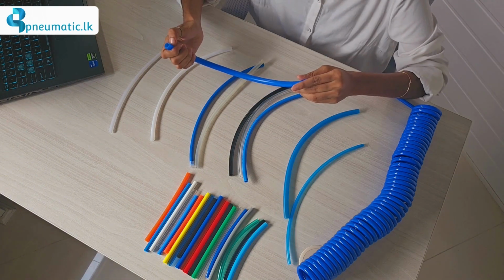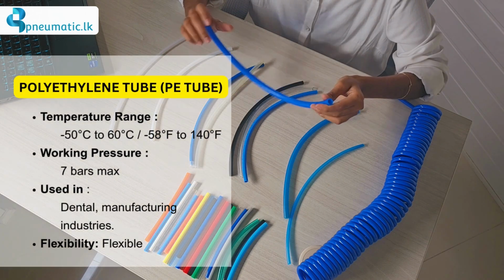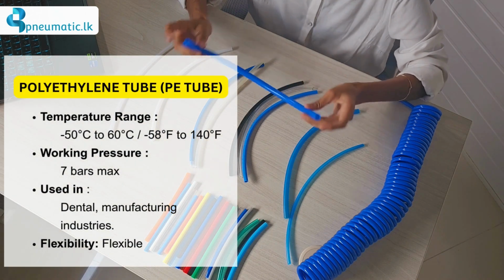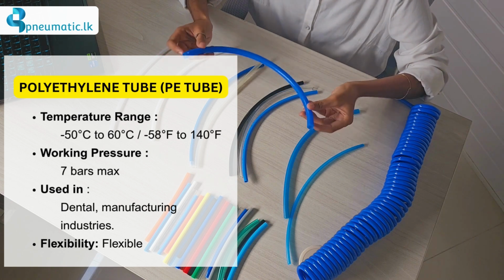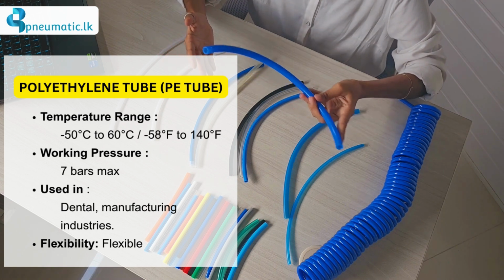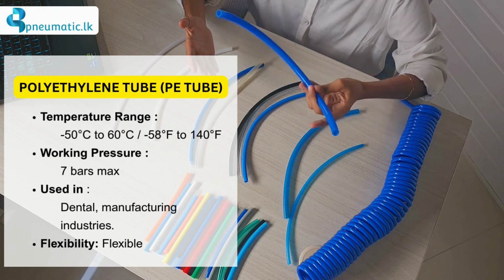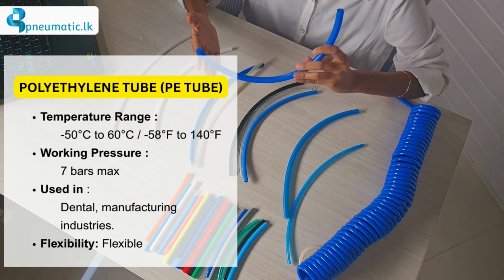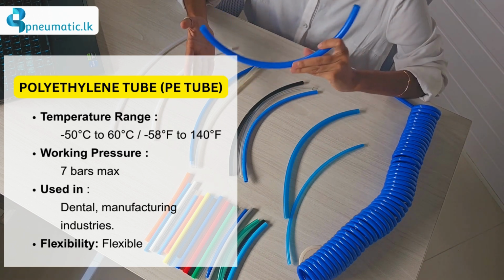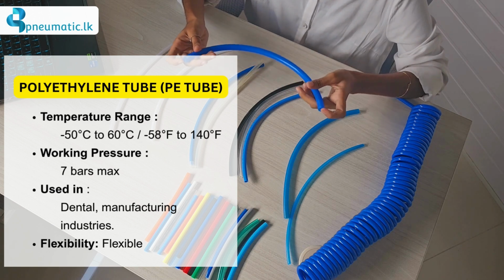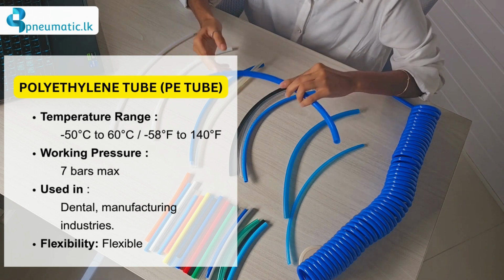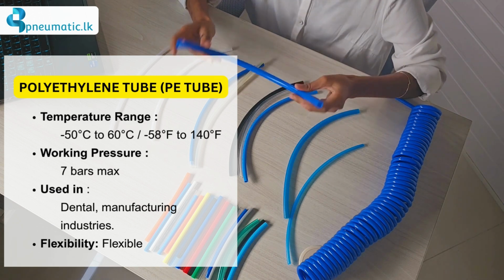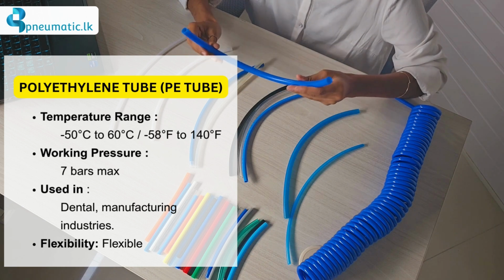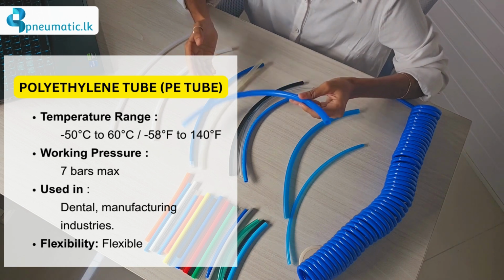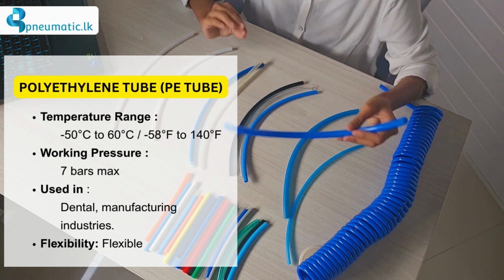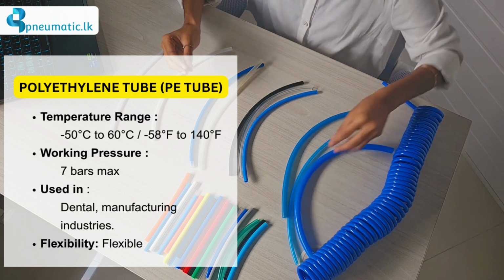When we are talking about tubes, we have to consider the flow temperature as well as the pressure we can send through these tubes. The temperature range for sending compressed air through these tubes is from minus 50 Celsius to plus 60 Celsius. The maximum pressure PE tubes can handle is around 7 bars, but it depends on the thickness and the application for which we are using these tubes.